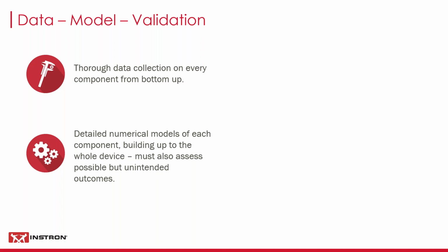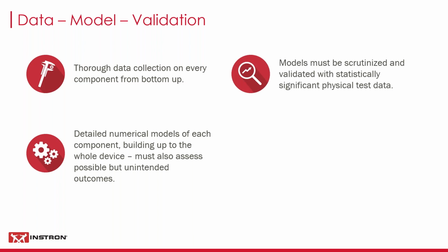The other thing is, and certainly the way I read it, that guidance document also does drive you to assess some of the, shall we say, not probable, but possible outcomes. They're not the intended use, but they could happen. You've got to cover the realistic possibilities. So those models then have to be scrutinized and validated, and that's where we come into that really quite challenging area of testing stent structures themselves.